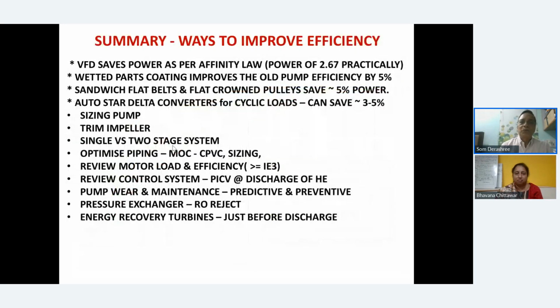Summary, to improve efficiencies: a VFD saves power as per the affinity law, as I have said. These are all actions that I am proposing now that will improve efficiency. We can have hydrophobic, non-erosive coatings on the pump wetted parts to improve by 5%. Sandwich flat belts against V belts give you 5%. Auto star delta converters: wherever you have cyclic loads, sometimes you need full flow, sometimes half the flow because half the reactors are off, and you find the motor is running at less than 50%. You can have an auto star delta converter.